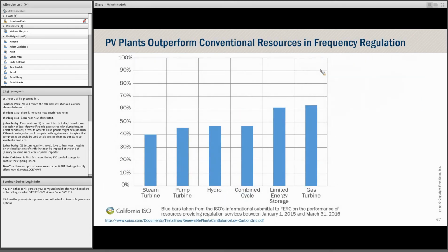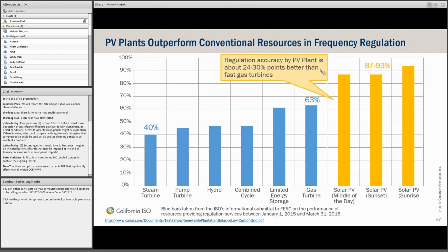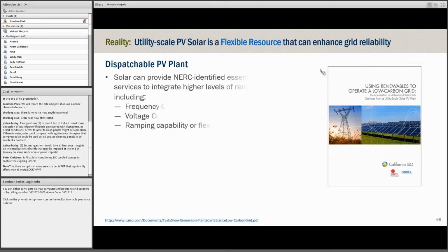In fact, you should ask how good are the results. So here is the accuracy of frequency regulation from CAISO from various different generation devices. For example, for a steam turbine, the accuracy is 40%, which means it can follow that signal 40% of the time. Think of it that way. And gas turbines, which are really fast, can do about a 63% level of accuracy, whereas for the PV plants, the regulation accuracy is about 24 to 30 points better than fast gas turbines. Now, there is no magic here. This is really power electronics that is able to follow that quite well. So not only can the PV plants provide reliability services, they can actually outperform conventional generation in that regard. So that was the main result.